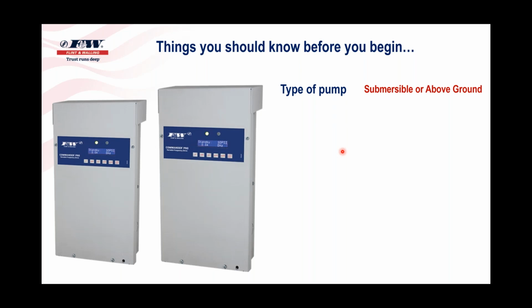Anyway, obviously this first one's kind of a no-brainer. When we program a drive, we want to let this drive know, are you going to operate a submersible pump, which is very, very common, or are you going to operate an above ground pump, like, say, a centrifugal type pump? So we want to know what type of pump we're going to operate. That's a no-brainer. Then we want to know what type of motor.